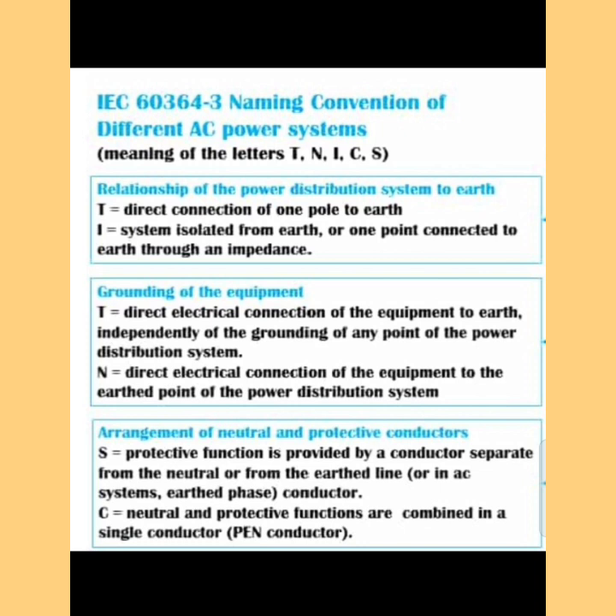What is the meaning of the very first term? The very first letter basically gives you the relationship of the power distribution system to the earth — it talks about the source. It has two options: T, which stands for Terra (Terra means Earth), meaning direct electrical connection of one pole to earth; or I, meaning the system is isolated from earth.